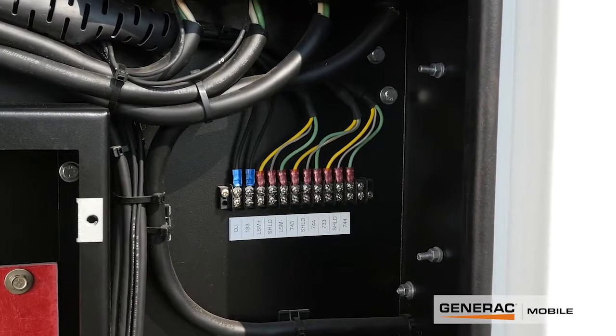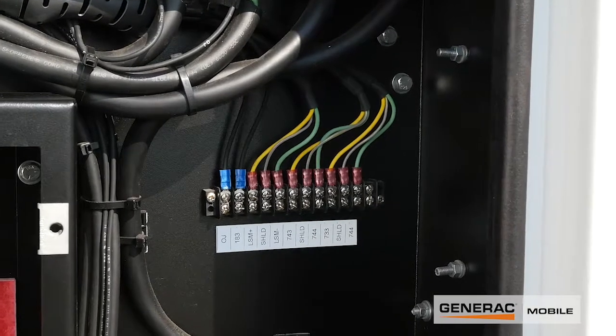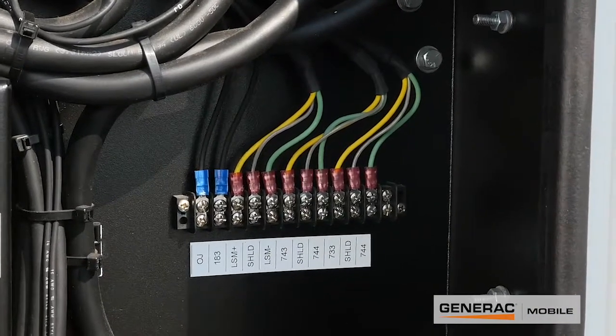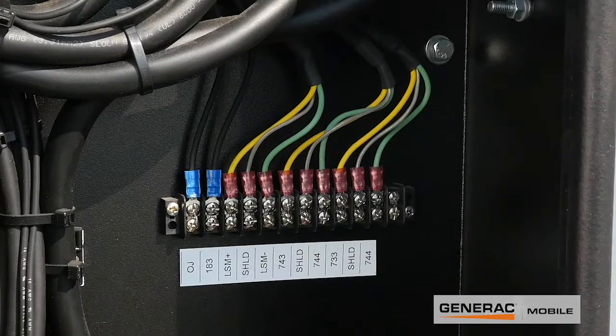The six colored wires on the far right are your standard CAN connection between any COM app or similar MGG 450 units. The three colored wires to the far left are for analog load sharing with a third-party controller such as Deep Sea or DEIF. And the two black wires at the far left of the terminal block are for a remote start connection.